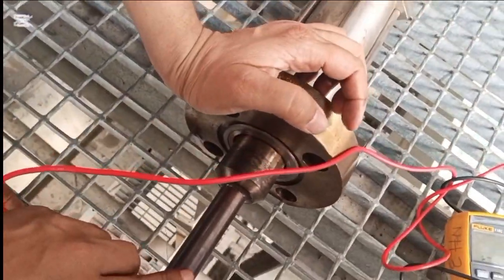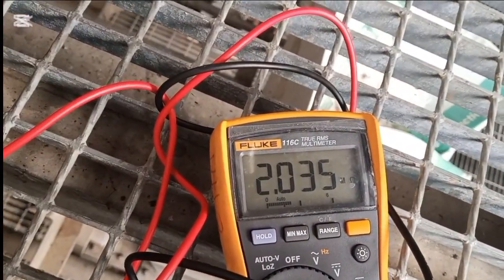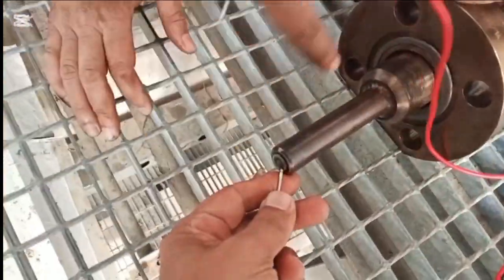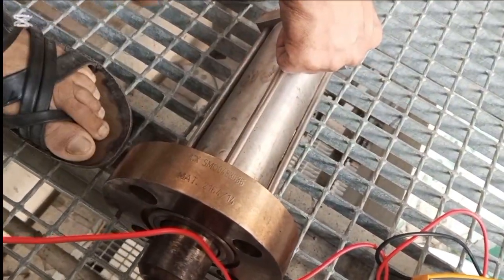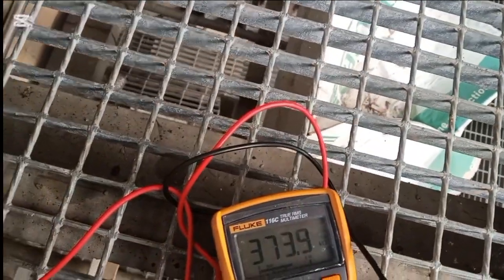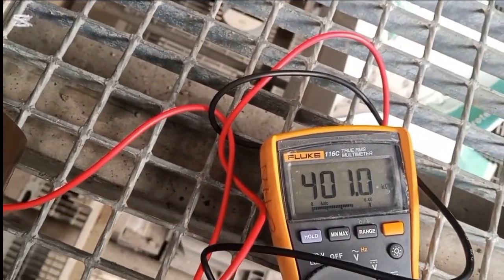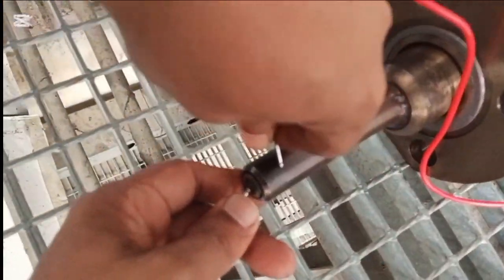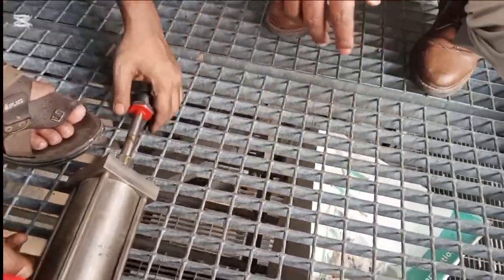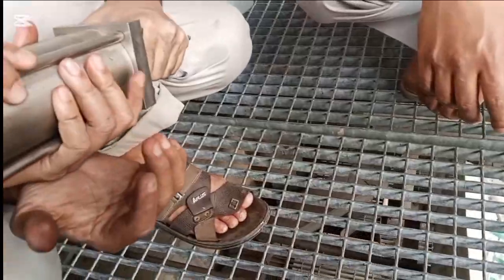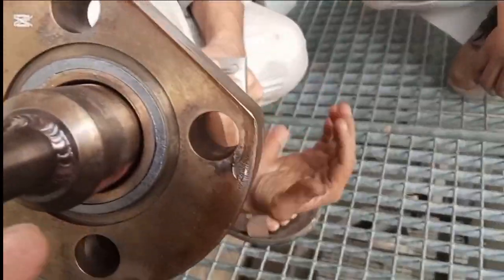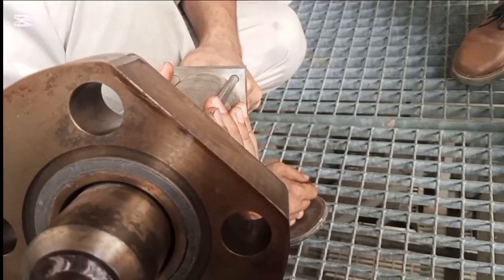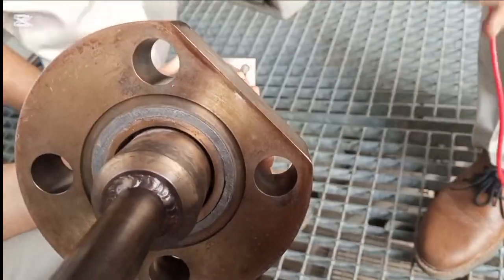for connection, easily connected with the gas turbine. It is like a boiler. This is showing resistance. After that we again measured the electrode continuity from one side to another side, but we see that the resistance is higher valued. So the electrode inside this spark plug may be not okay. This is the complete spark plug unit.